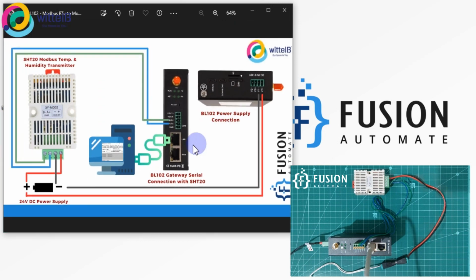To power up this transmitter, we have also given a 24 volt DC power supply to this transmitter. So both these devices are powered up with the 24 volt power supply, and this transmitter device is connected serially to this gateway with two cables. The cable color is green for B minus and blue for A plus, as you can see here in the video as well.